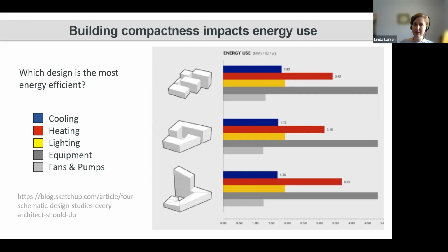So building compactness is going to impact energy use as well. You can see in this little graph how these three building types are different in how much energy they consume. You can see here on the top a bit of a difference in the heating load. The heating load is greatest for this building down here, and least for this building, which is more compact. You can also see that it impacts the cooling load slightly as well, whereas the lighting and equipment stay relatively the same.